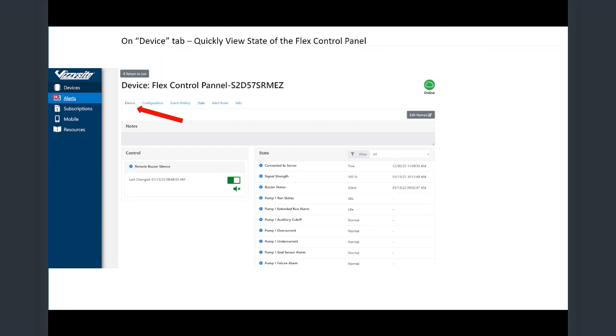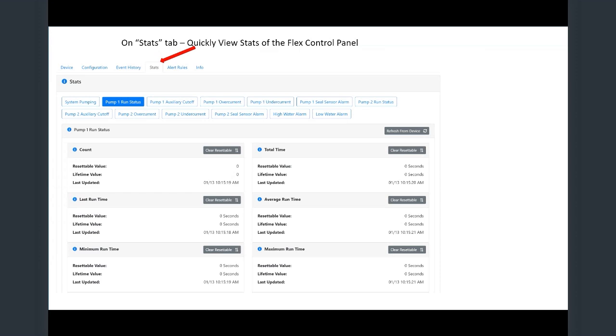Or undercurrent as well. And then you can also hook up our little floor water spotter systems to that, so if you have a leak, you could shut your pump off too. So our Flex system can pretty much do everything and tell you if your pump failed. If we say, hey, voltage should be going to your power relay, but guess what? We're not finding any amps. That means your pump has failed. So we can give you pump fail notifications as well.